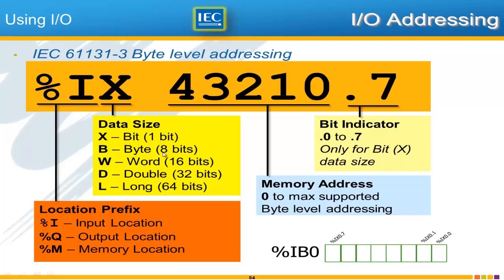The next part of the address is the data size where X means a bit, B means a byte, W means a word 16 bits, D for double 32 bits. And L for long 64 bits. So while the numbering scheme coming up next here is numbering the number of bytes, you can have a data size that uses several bytes.